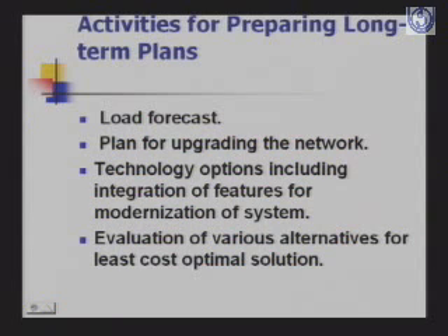Then the global load forecast is divided into a spatial load forecast, because in distribution systems we have to do spatial planning. We have to plan for small areas, so we divide the load forecast into smaller grids, forecast for smaller areas, and we superimpose it on the system, see what will be the losses in the existing system if this demand was also to be met, and generally that the system will get overloaded, and considering this we plan for upgrading the network, and those plans are prepared where we will need upgradation for meeting the forecasted load as well as for reduction of losses, and we include various technology options for modernization of the system.